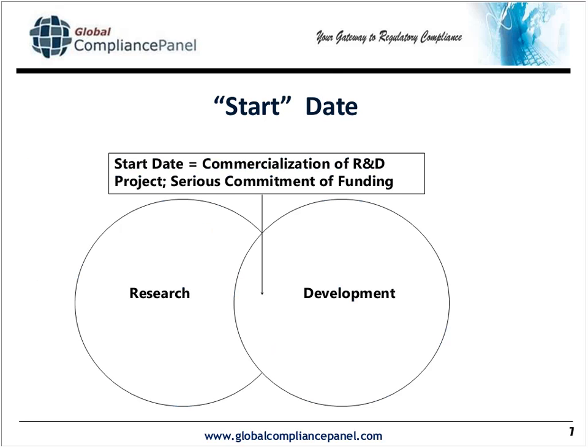Now, this is kind of a poor copy of Kimberly Troutman's discussion years ago on design control, where she showed the overlap between research and development. You as a company are responsible to have a start date for design control. And everybody asks, well, what is that? And what does the FDA expect? The FDA expects you as a company to put in a date that's reasonable, a date that obviously doesn't show you're trying to escape the design control requirements.